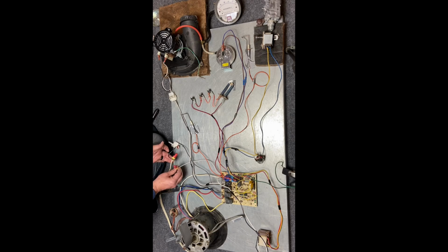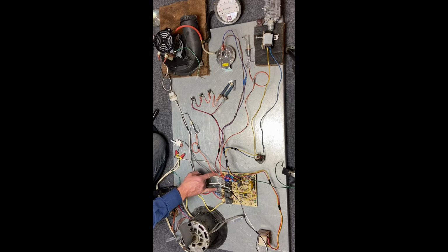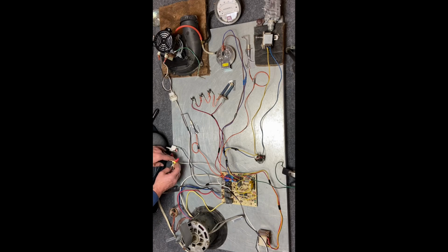So this is particularly on what we call a pigtail or a plug. A lot of codes don't allow you to use this, but if you do have a plug, it's called ribbed to white, smooth to black. And this is a ribbed wire, and it connects to the white wire. And this wire is smooth, and it's connected to black. Ribbed to white, smooth to black. These 2 wires eventually get to our control board under primary and neutral. So if we follow the white wire, the neutral wire goes to the neutral terminal on our control board.